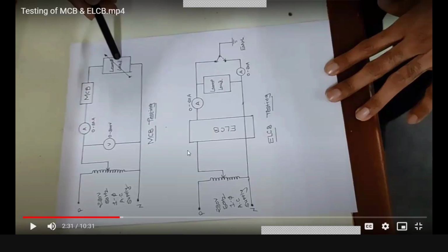This is the circuit diagram for ELCB. Again, this is the supply phase and neutral, this is the variac, and this is the variac phase and variac neutral. This ELCB is connected between the phase and neutral, and this ammeter is connected in series. This is the lamp load. Another ammeter will measure the neutral current, and this ammeter will measure the phase wire current. This is the DP/DT switch, students.